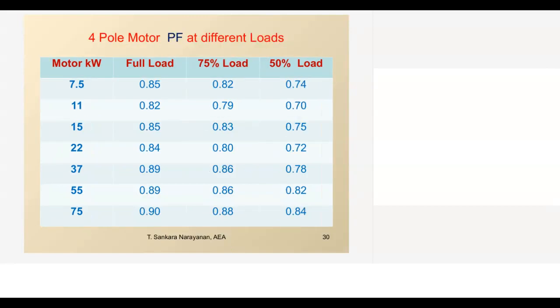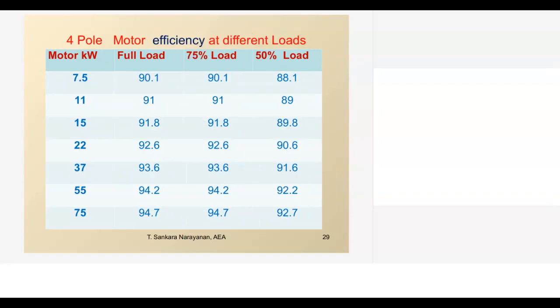Similarly, all these motors have different power factors. Why have we put this? Many a time we take a tong tester and calculate root 3 VI cos phi. So for a 100 ampere rated motor, if the operating load is only 60 ampere, what power factor are we considering for root 3 VI cos phi? The motor is designed for 0.9 PF. The system is maintaining 0.98 PF. So the full load ampere is 100 ampere. I am measuring that the operating load is only 60 ampere. What power factor should we take?